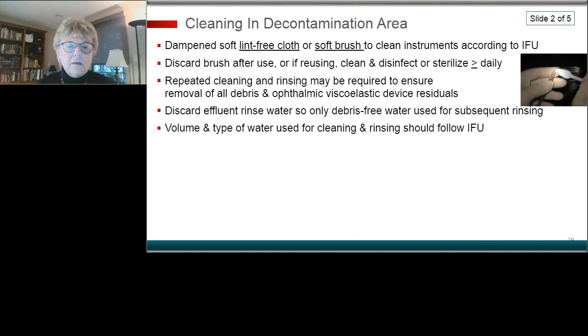Discard the effluent rinse water so that only debris-free water is used for subsequent rinsing. Again, trying not to contaminate that rinse water. Volume and type of water used for rinsing should follow the IFU from the manufacturer. Many IFUs require critical water. What is critical water?